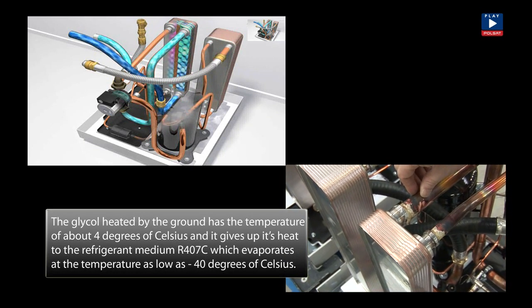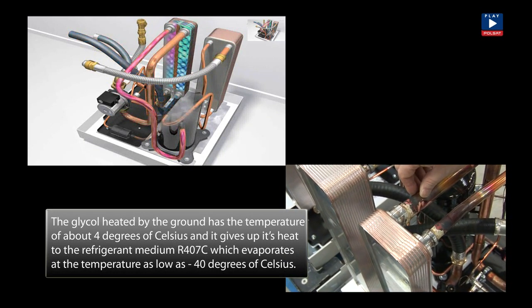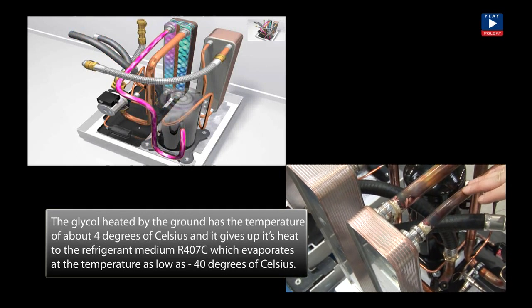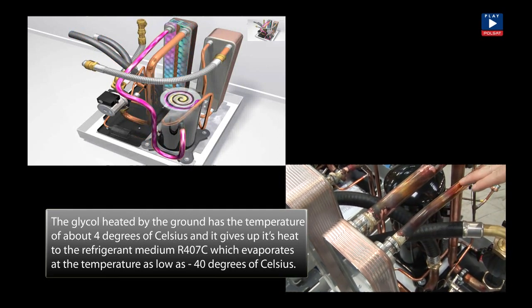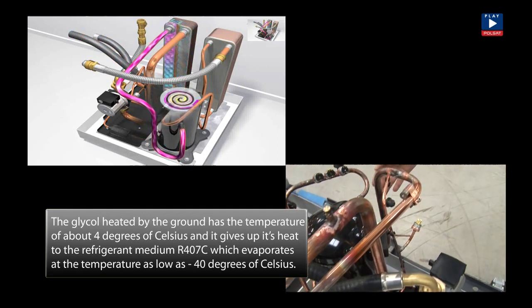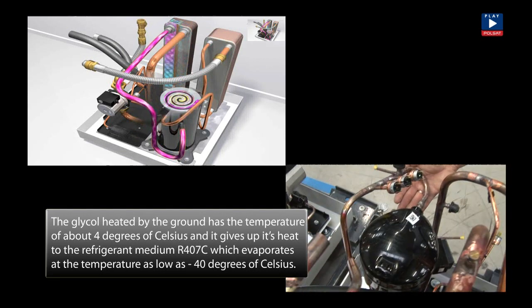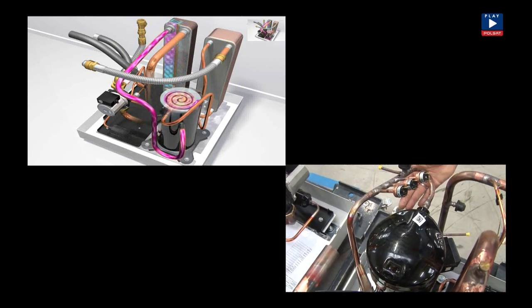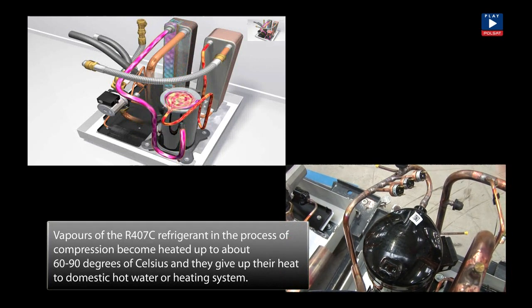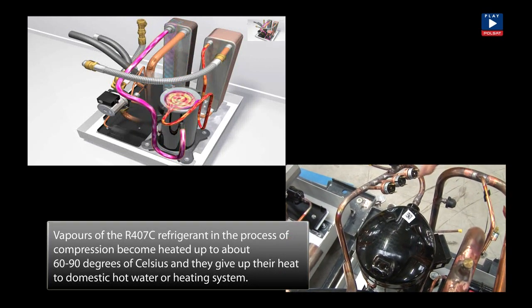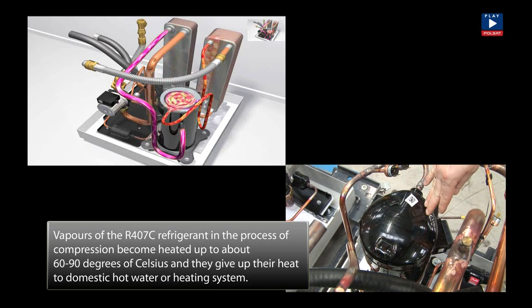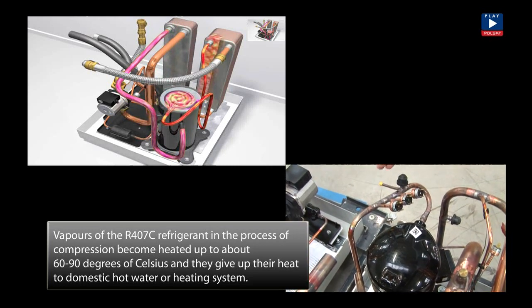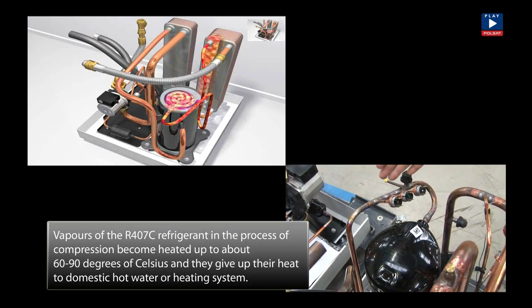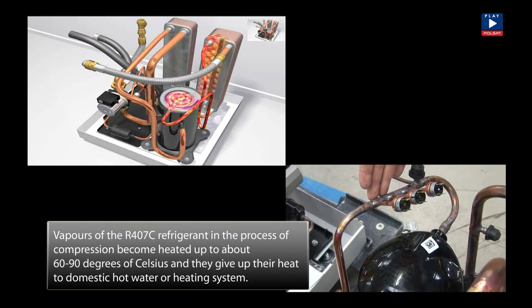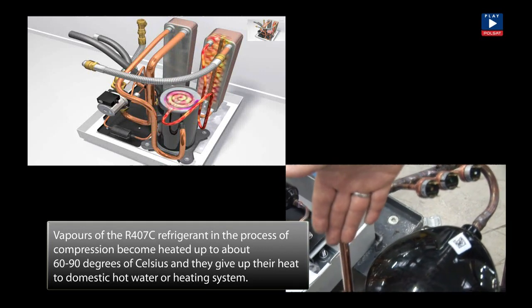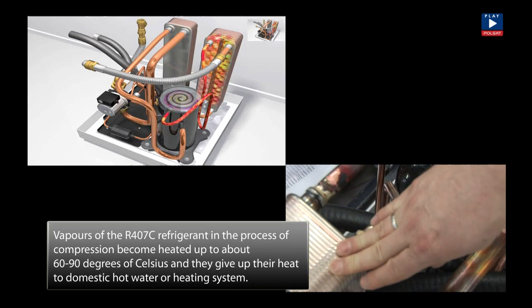heats the refrigerant, which through those pipes in gaseous form enters the compressor. The compressor greatly increases the temperature and pressure of the refrigerant. On leaving the compressor, the temperature of the refrigerant is from 60 to 90 degrees Celsius. The high temperature refrigerant now enters the second stage heat exchanger known as a condenser, where it gives up its heat to the radiators, underfloor heating or domestic hot water.